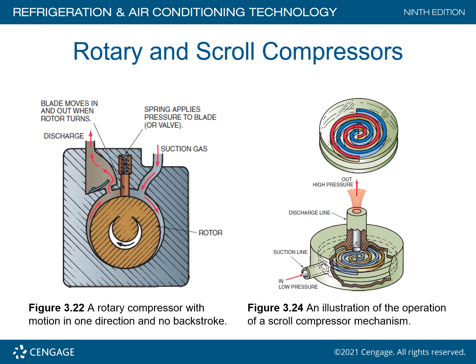So in this case here, remember refrigerant now is going to go in the fixed scroll as a low pressure, low temperature vapor. And of course this orbiting scroll is going to compress around the stationary one, and it's going to push the refrigerant vapor through this center hole, and that of course will exit the compressor in the form of superheated gas.